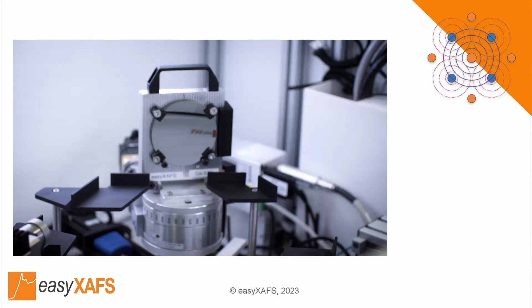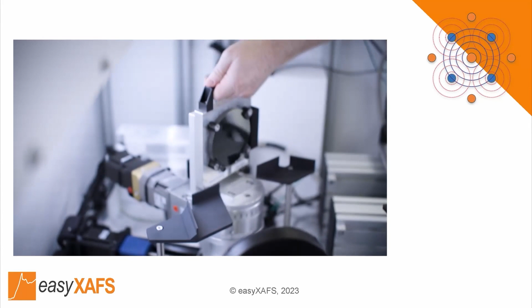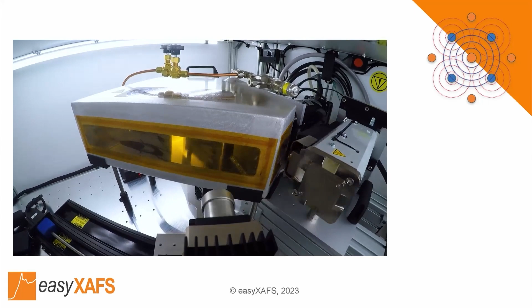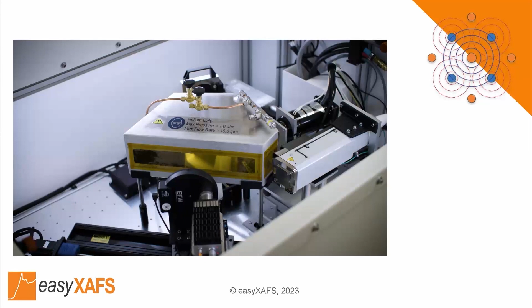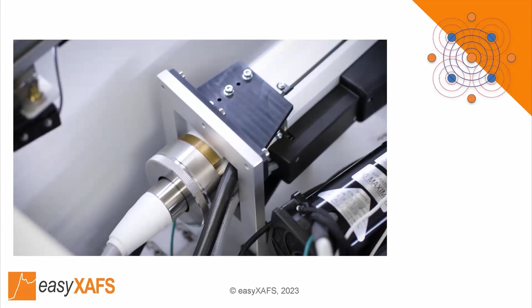All of our hard X-ray systems utilize spherically curved crystal analyzers. These come pre-aligned and mounted to their own individual cartridge plates. Swapping between crystals is a simple matter, so in a matter of minutes you can be switching between different elements and energy ranges. Using a point-to-point focus geometry, the system steps through different angles to record the energies of the spectrum. A large area SDD detector allows for isolation of the harmonic of interest in order to boost the signal to background ratio. For best possible flux and resolution in XAS mode, we have our 1200 watt XRD style tube.